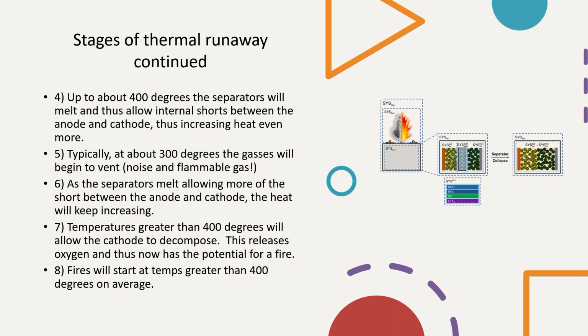Stage 4 of thermal runaway is up to about 400 degrees Fahrenheit. The separators will start to melt. Now, we just kind of talked about that. The problem with that is when the separators start to melt, we start to have small little shorts between the individual plates of the battery pack there. And that adds even more heat. Stage 5 is typically about 300 degrees Fahrenheit. Gases will begin to vent. Noises, it's a flammable gas. We talked about all that.